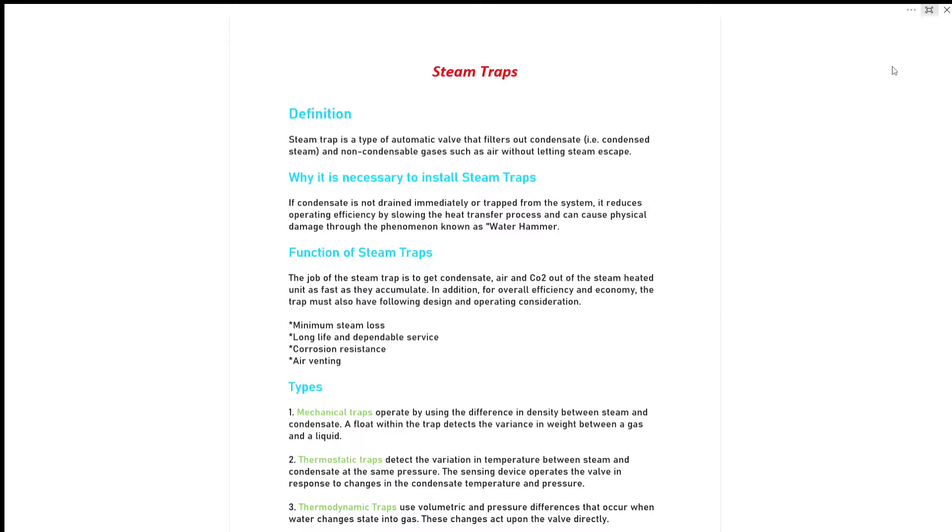Why is it necessary to install steam traps? If condensate is not drained immediately or trapped from the system, it reduces operating efficiency by slowing the heat transfer process and causes physical damage through the phenomenon known as water hammer.